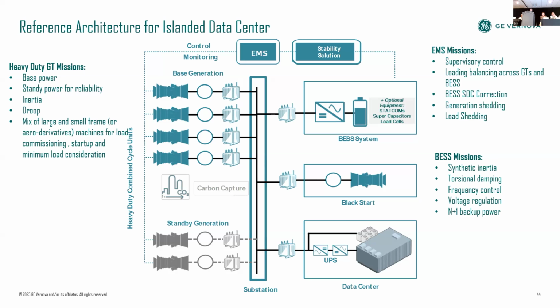Another aspect that is part of the architecture is the EMS, which is basically a higher-level coordination system that assigns the responsibility between the BESS system and the conventional generation systems to dispatch power balance on the longer time scale. On the shorter time scale, when it comes to the millisecond-level response, the relief will come from the BESS system. Right?